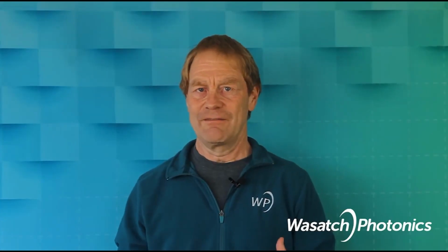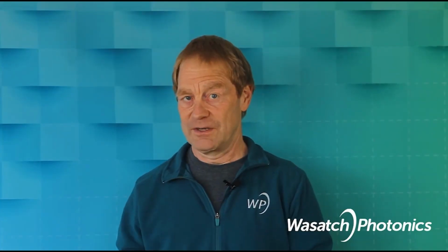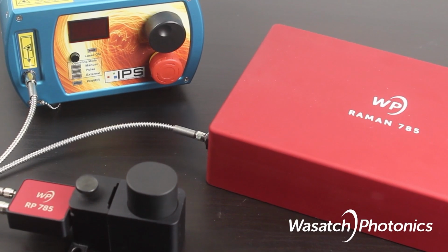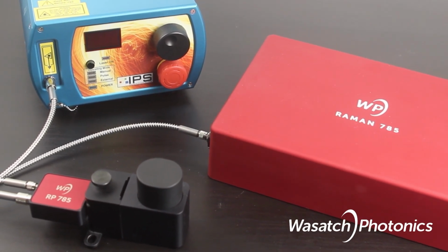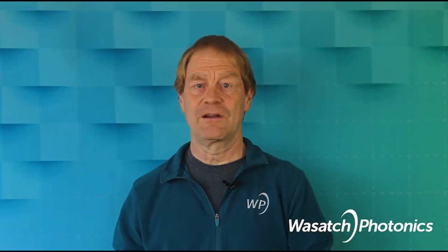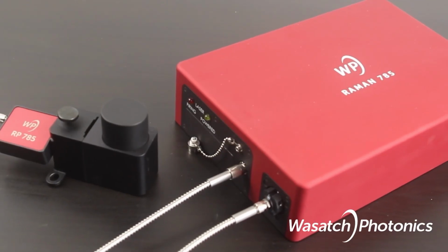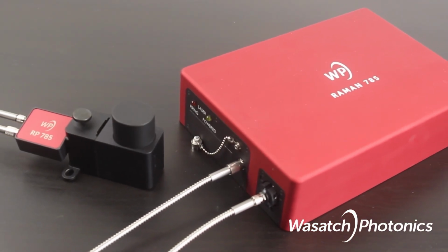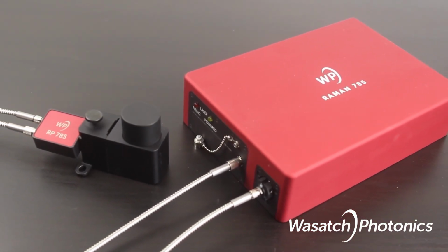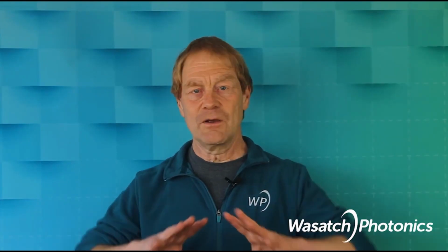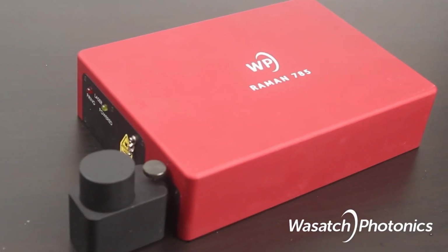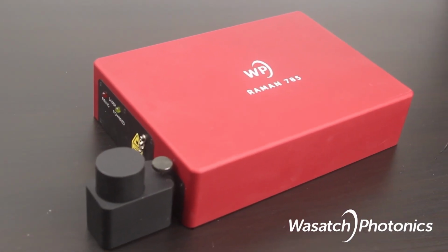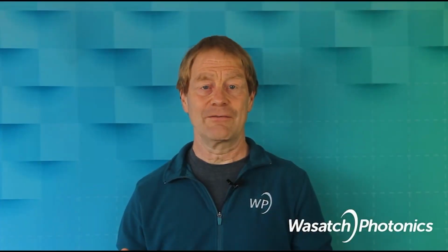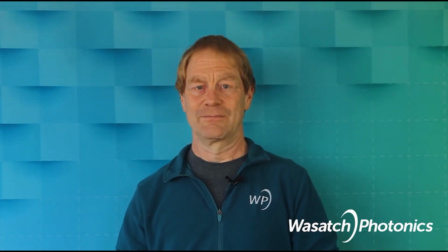Wasatch Raman systems are available in 3 main configurations. The system can be completely modular with separate laser, probe, and spectrometer. Our most popular system already has the laser built right into the spectrometer, but the probe is still fiber coupled. And finally, the system can also be completely integrated with the probe and the laser, both inside the spectrometer. But whatever system you have, the setup is very similar, with only some minor differences. So let's start by connecting the laser.